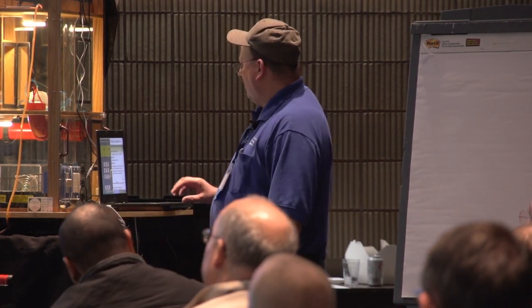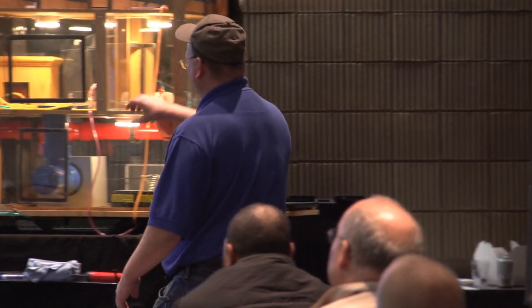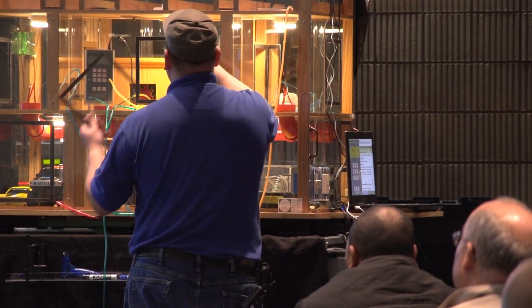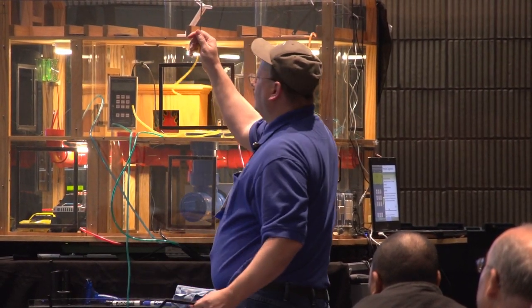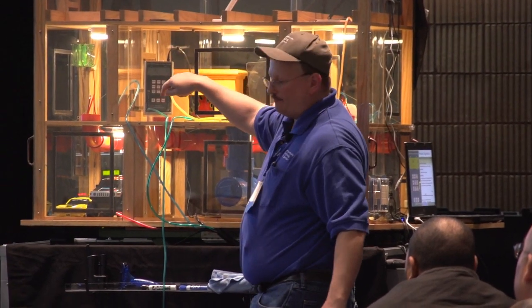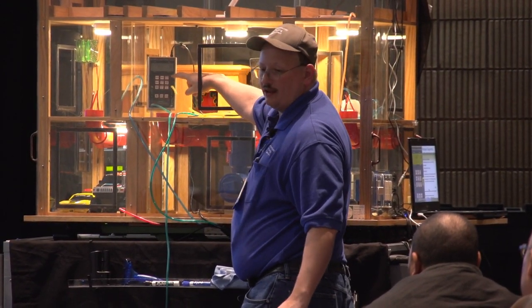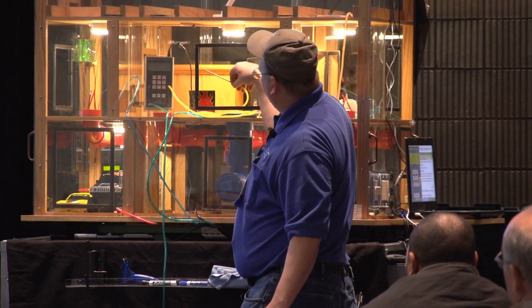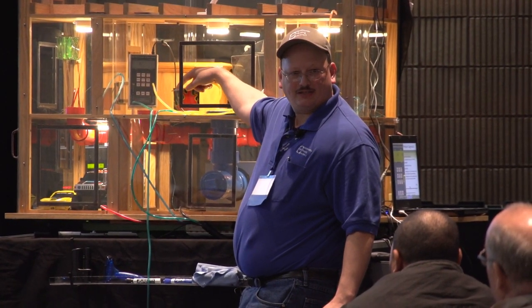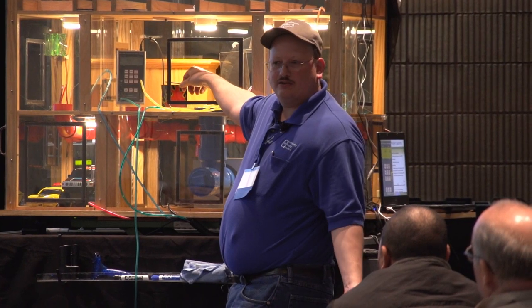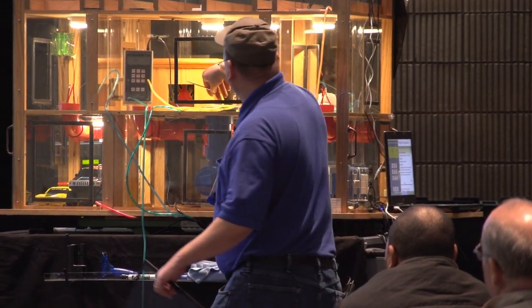We know that the other end of the green hose, connected to the bottom, is going where? Outside. What about this yellow hose? You see it's connected to the input on channel A. Where do you think the other end of it is? Inside or outside? Inside. It's just laying right on the living room floor. So basically, the top port that has the yellow hose, the end of that was in the same place as the bottom port, right? So there's no pressure difference. Is everybody good with that?